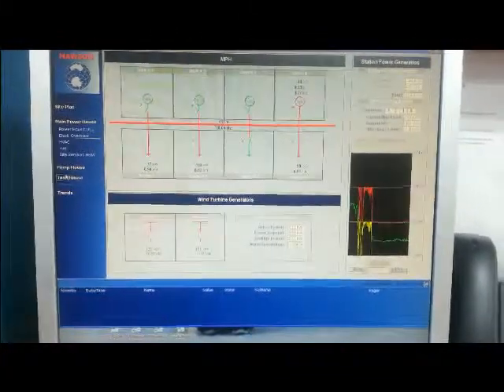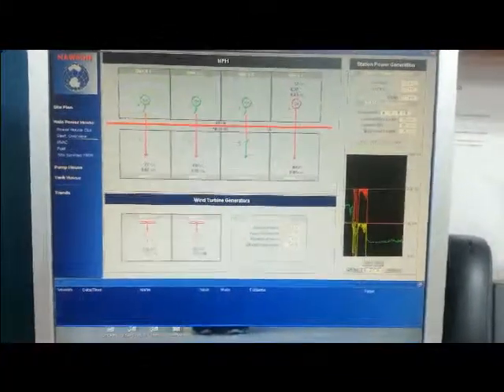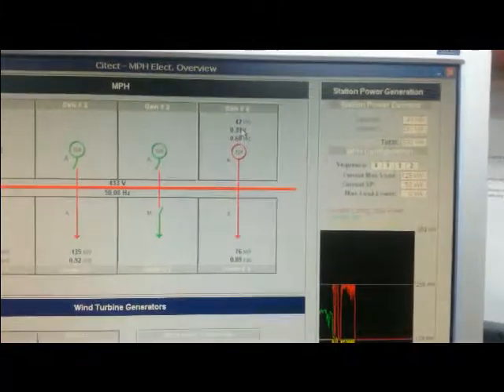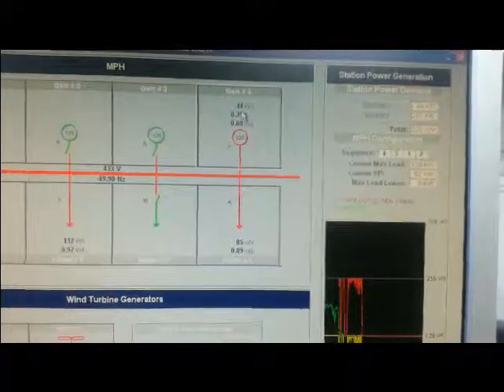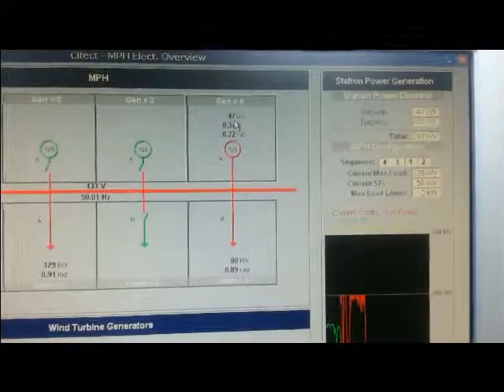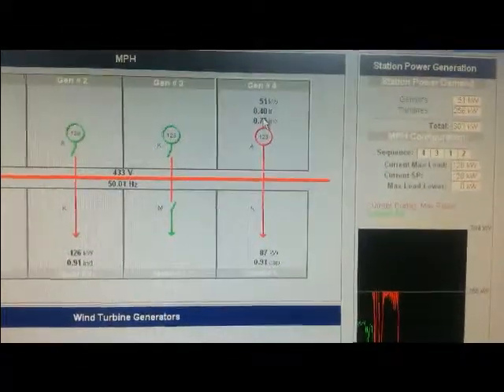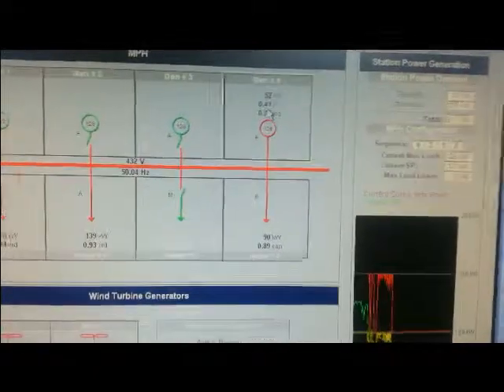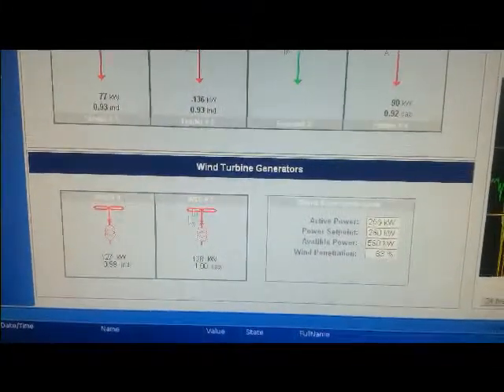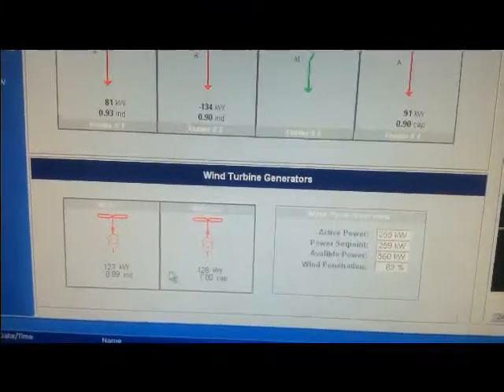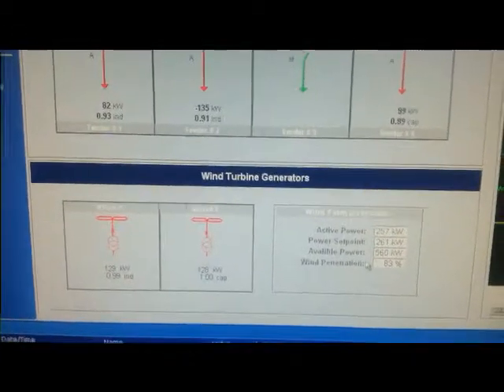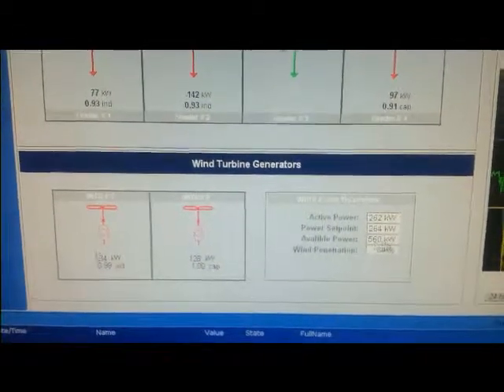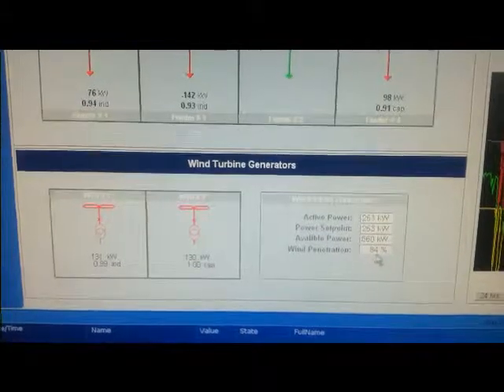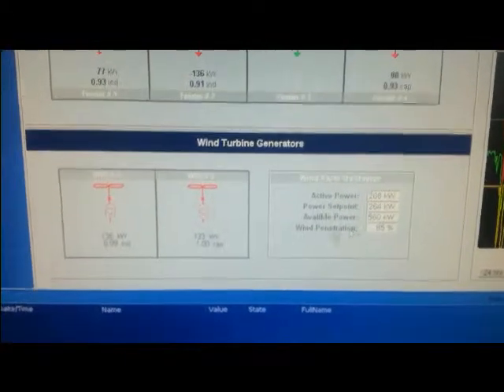So here we are in the MPH at the moment. Got nice wind, I'm just running genset number 4 here, running pretty much the minimum load it can run, about 50 kilowatts. It's basically just there for the wind turbines to synchronise to. Our two turbines are doing about 130 kilowatts. We've got enough wind at the moment to do 560 kilowatts. We're using about 84% wind energy at the moment.